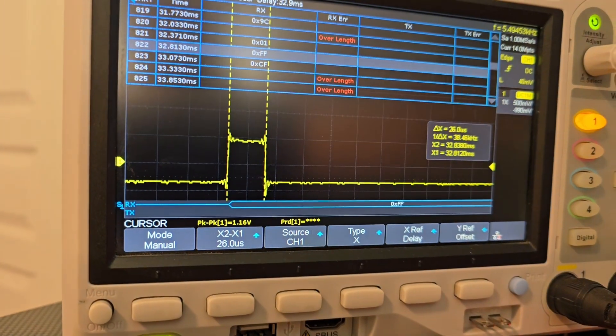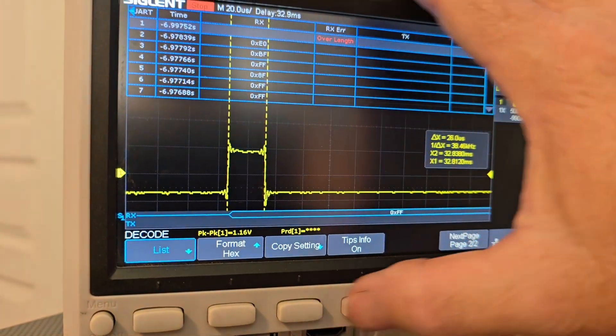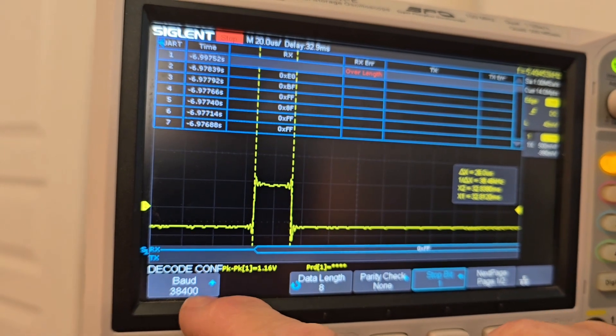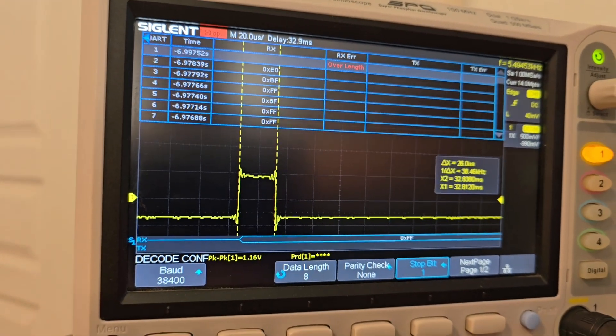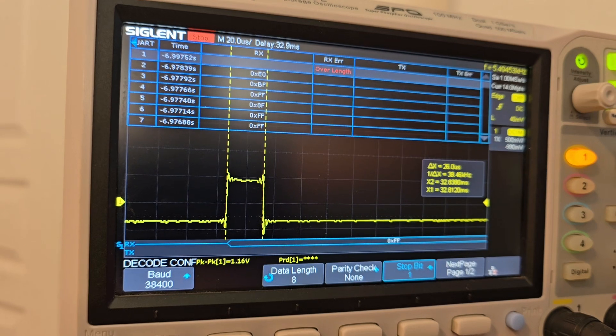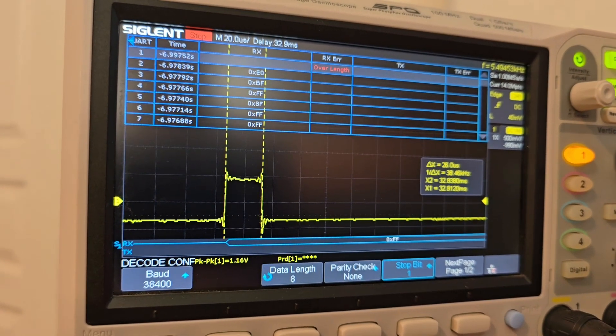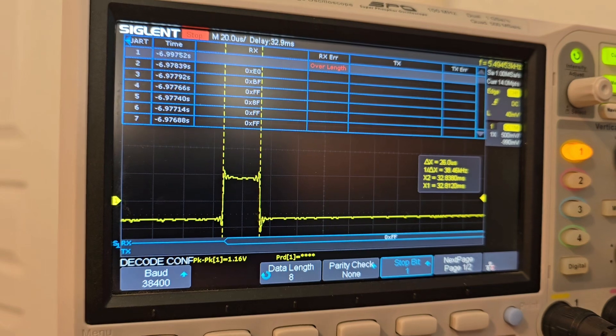So 38.4. And then in the decode thing here... what was that signal? Nope. I'm still getting used to this thing right here. Baud rate. So 38.4. And as soon as I did that, I'm like, oh yeah, that is what it is. You program VFDs and whatnot that communicate to the LEN bus here. You program them for a baud rate of 38.4.